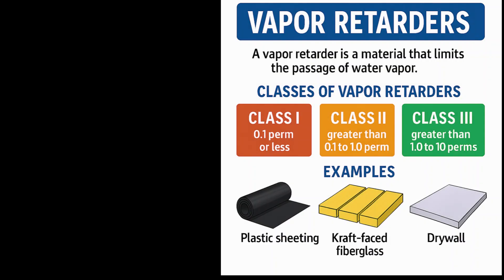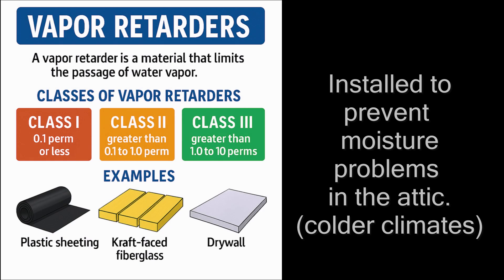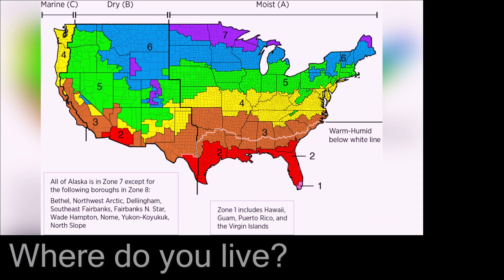One thing you need to know to determine how much net free ventilation area you need for your house is whether or not you have a vapor retarder. The first tip to see if you might have one without even having to go into the attic is to determine what climate zone you're in.